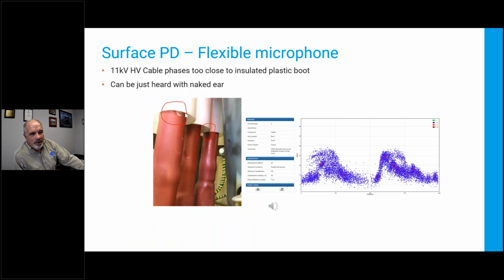Here's an example where they had these little plastic boot things, which I've never seen anywhere else, and now it's causing a discharge. Even though it was just an insulator, an insulator in the wrong spot was causing discharge. And a nice phase resolved plot. If I were to play the sound clip, it sounds just like it should. Big difference, 35 dB versus 0, so 1,000 times peak to the noise ratio. That's a nice clean phase resolved plot. And there's the sound.